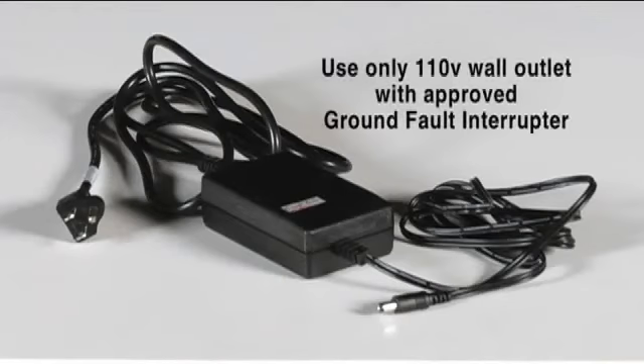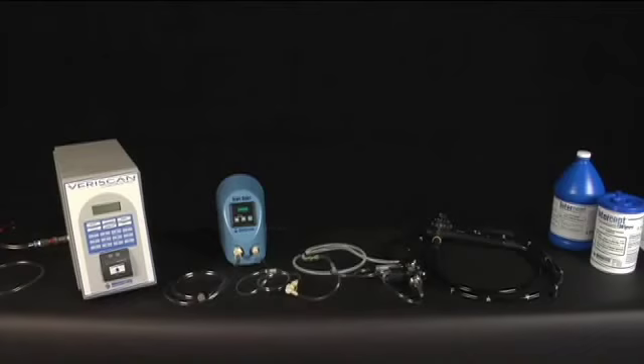Scope Buddy should be plugged into a 110-volt electrical wall outlet that includes an approved ground fault interrupter prior to operation of the pump. The tubing hookups, hookup extensions, and fluid intake line are not autoclavable and must be reprocessed by low-temperature disinfection only. Scope Buddy is designed to be placed on a countertop or mounted to the wall by using the supplied wall mounting bracket.